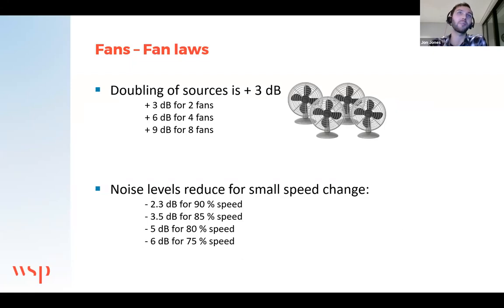So understanding how the number of sources and the amount of energy affects the overall noise level is important, particularly when we're considering the number of noise sources in a building services environment. So for example, if we're talking about fans or any noise source, the higher the number of fans that we have, obviously the higher the noise level that we need to consider. When we are looking at noise impact and assessing the noise from plant, it would be a cumulative level that we're interested in, so it's always important to know the number of fans that we're looking at. Alongside that, the noise data provided for the fan in question should be representative of the intended duty that the fan will operate at in situ once it's installed.